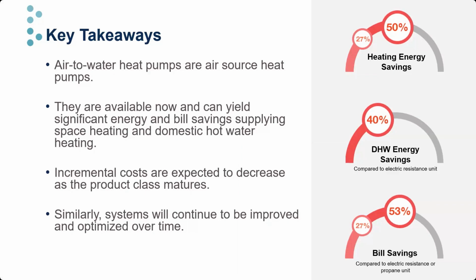The site with domestic hot water heating supplied by the heat pump saw 30% of their DHW needs supplied by the high-efficiency heat pump, yielding energy savings of about 40% that will likely be higher in the average home. Bill savings range from $450 to $1,400 per year, or between 27% and 53%. And while the payback period is at or beyond equipment life, upfront costs are only expected to decrease as this product segment matures. Similarly, we could expect further improvements in system design, construction, and controls optimization to potentially yield greater operating savings through performance gains, as we've seen with traditional air-to-air heat pump systems. Next slide.